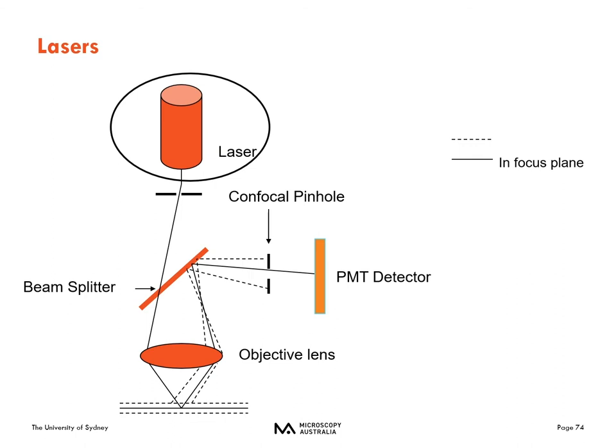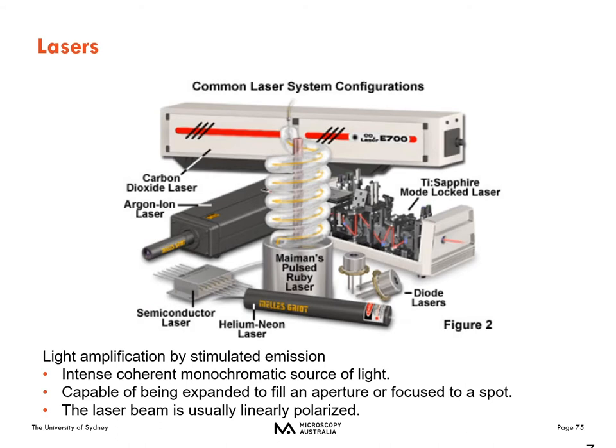The laser is the light source at the top of my schematic. There are many, many different lasers available. It's a very intense, coherent, monochromatic source of light. So instead of a white light source like we use in fluorescence microscopy or even brightfield microscopy, this is just going to be a single wavelength, typically. That coherent light source will be expanded to fill the back aperture, or it can be focused down to a very small point of light — and that's what we need for scanning.